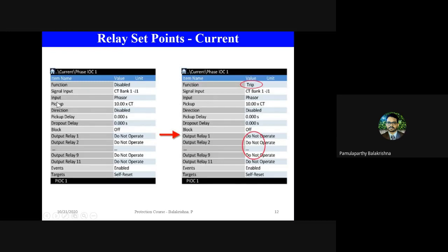The next most important is the pickup, or what we generally call the threshold. It defines the current level beyond which I should consider it an overcurrent for this function to execute. Usually that is configured as times the CT ratio. CT ratio, you might have heard, is the primary current over either 5 amperes secondary or 1 ampere secondary. Based on that, the primary fault current is converted to the equivalent secondary current. If 10 times the CT ratio, or 10 times the normal current, flows in the system, I am defining that as an overcurrent. So this particular function will execute, if it is enabled, when the current level reaches this value that is set here.